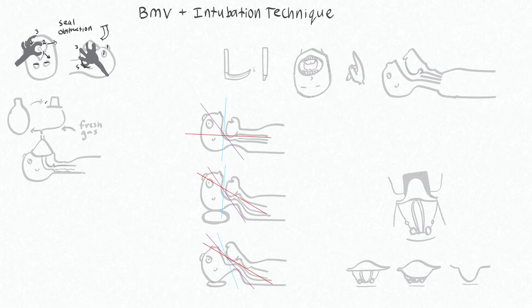Our circuit for actually delivering air or oxygen to the patient will look something like this. We'll have a bag and this is a valve which is adjustable pressure limiting valve. What this valve does is prevents pressure in this circuit from going above whatever you set it to. So let's set it to 20 centimeters of water and now any pressure in this circuit that builds up beyond 20 centimeters will escape out. So the air will leave the circuit so that the pressure in the circuit does not exceed 20 centimeters of water.